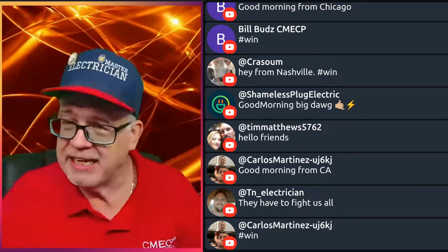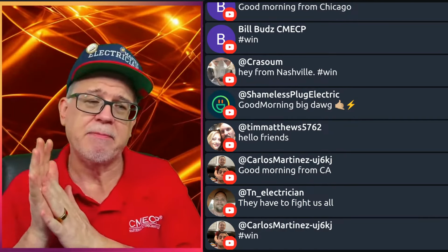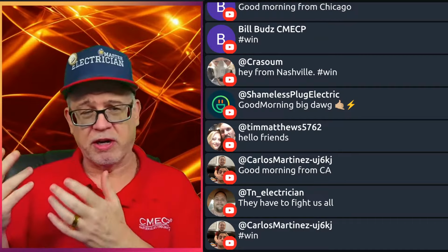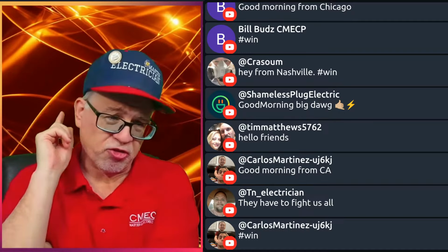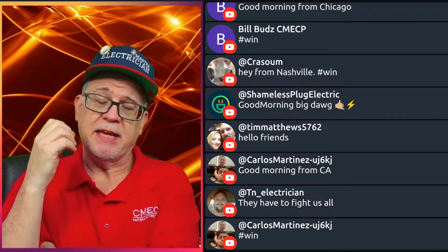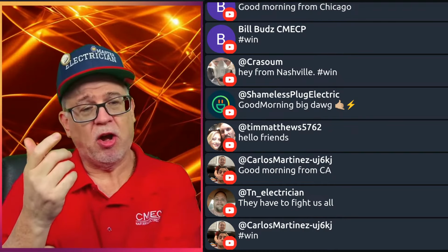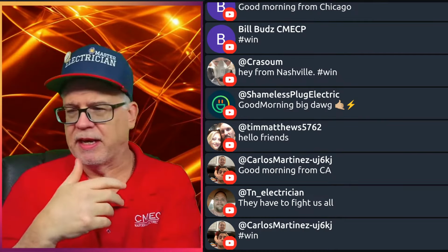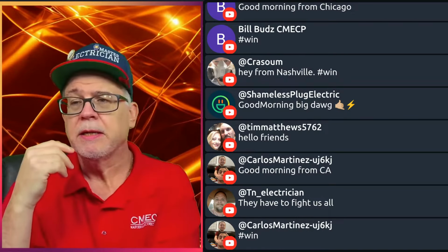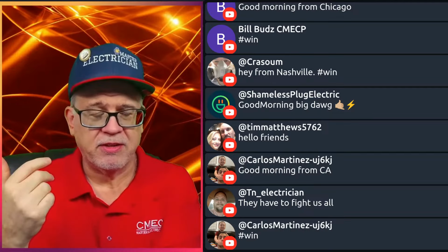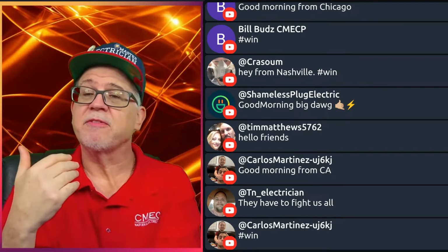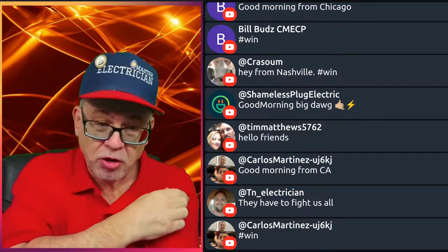You're not going to add any additional VA. That's something many people get confused with when they go finish a basement off and the service has already been established, assuming that the electrician knew what they're doing. If all I'm going to do is gypsum it and add rooms, just general use rooms, basements, bedrooms, whatever, then I don't need to add any new VA. It's not going to add any additional load to the service. Why? Because the VA has already been accounted for. That's why they do it this way.